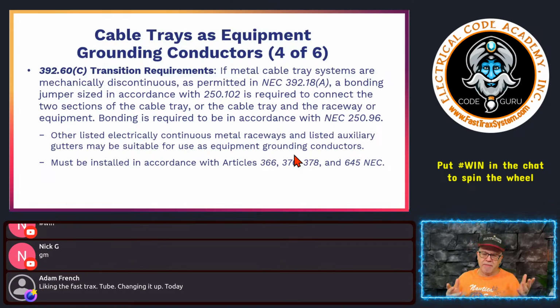The key takeaway here is that grounding and bonding is only as good as you follow the principal rules of establishing an effective low impedance ground fault current path. And so if I have a cable tray and I'm going to use it as an equipment grounding conductor, it's either continuous, it's either complete. If it's sectioned or discontinuous, then I'm going to make sure that I use bonding jumpers or follow the manufacturer's instructions to make it act as one, okay? No different than one continuous piece of EMT, for example, right? Same concept. All right, so keep that in mind.